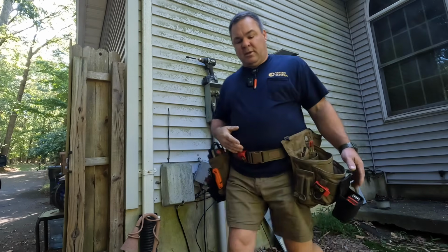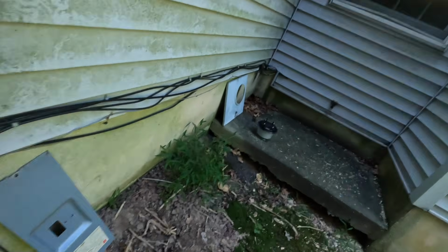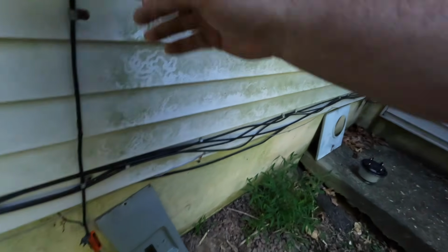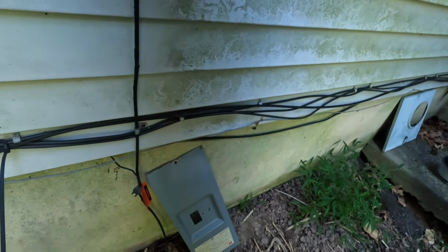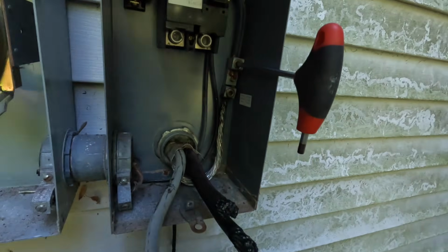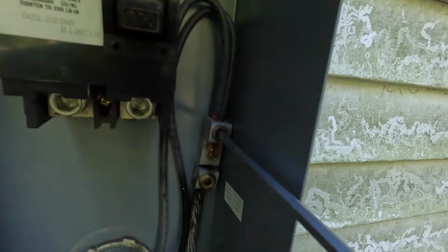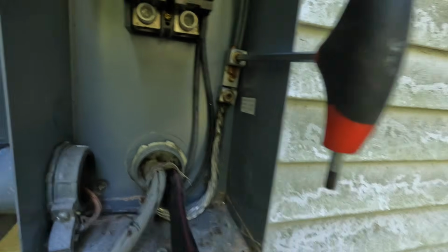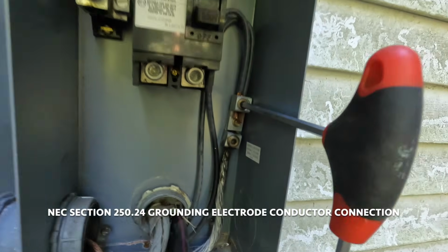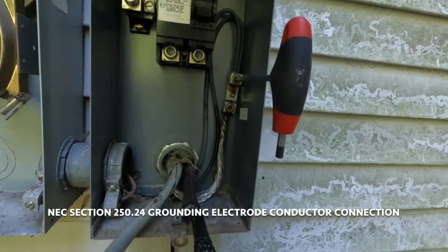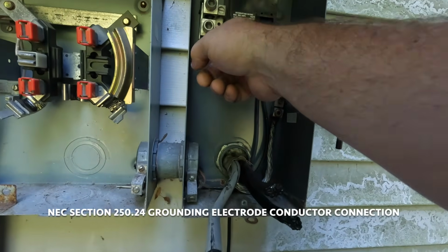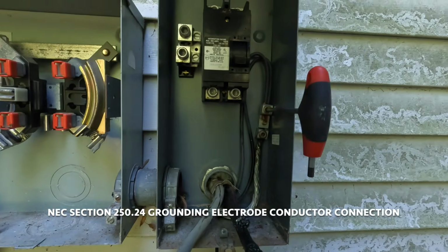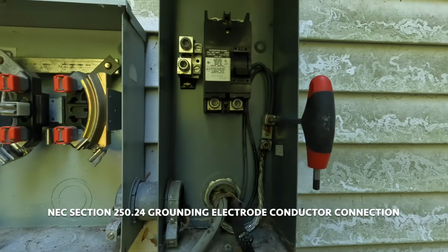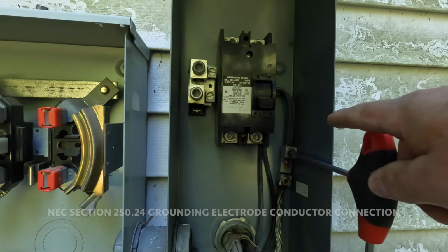Now here's a common violation. Not a huge deal here. It really isn't. This is the ground, or rather our electrodes. Well, the one electrode anyway. See the double tap on there? That would be no good by today's standards. Cannot do that. But apparently the inspector missed that, and he had another terminal right here to do that.